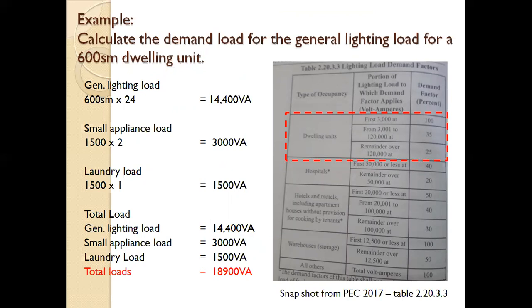We have another sample calculation of a dwelling unit with an area of 600 square meter. This is quite large. For the general lighting load, we have 600 square meter times 24, giving a total load of 14.4 kVA. Small appliance, 1.5 times 2 is 3 kVA. Laundry load, 1.5. So our total connected load is 18.9 kVA.